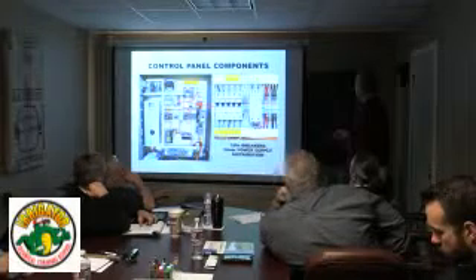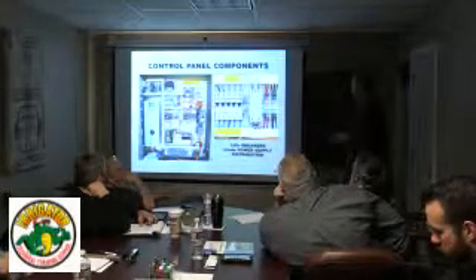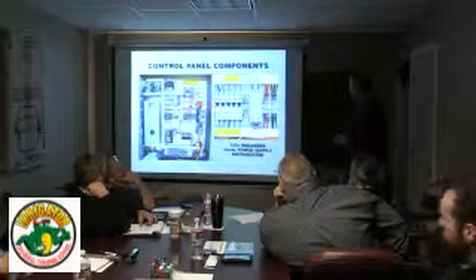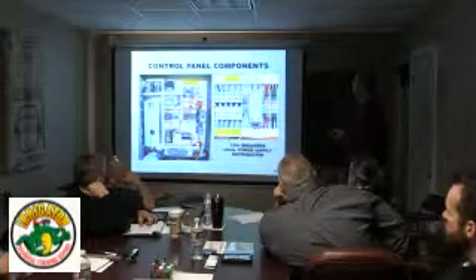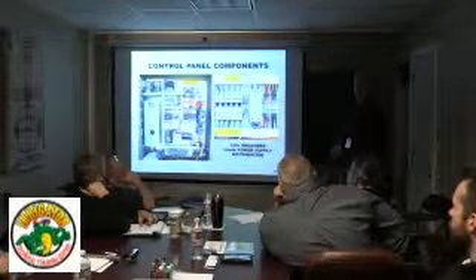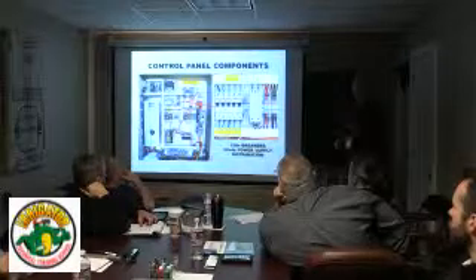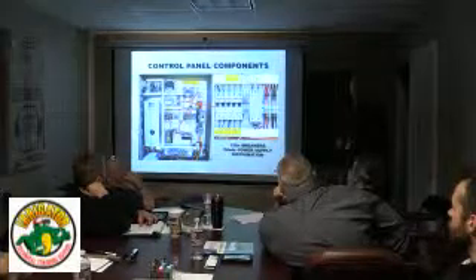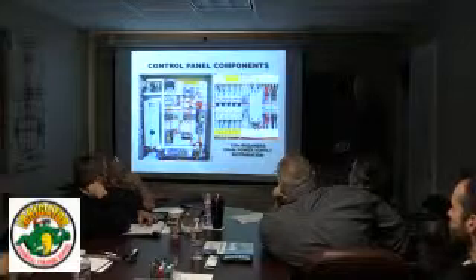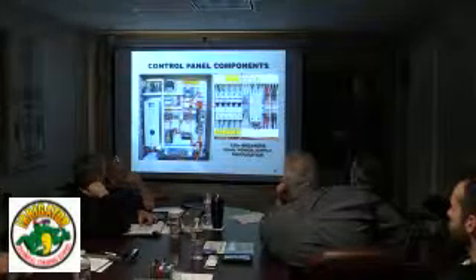And here we have our 24 volt DC power supply. This just comes down and jumpers into here, this one jumpers into here, and then we can take as many off as we need to go to the different 24 volt DC items: transducer switches, PLC, HMI touchscreen, whatever's 24 volt DC is plugged into here.